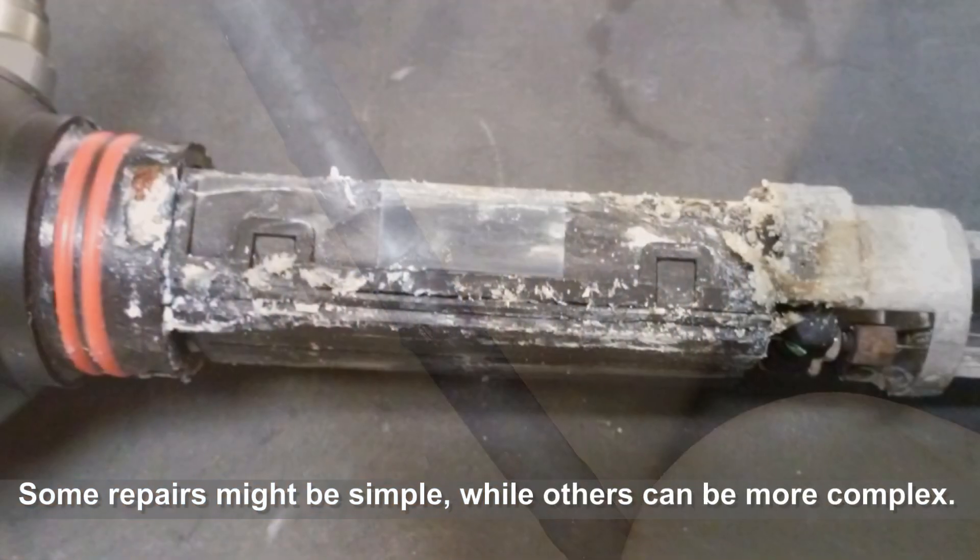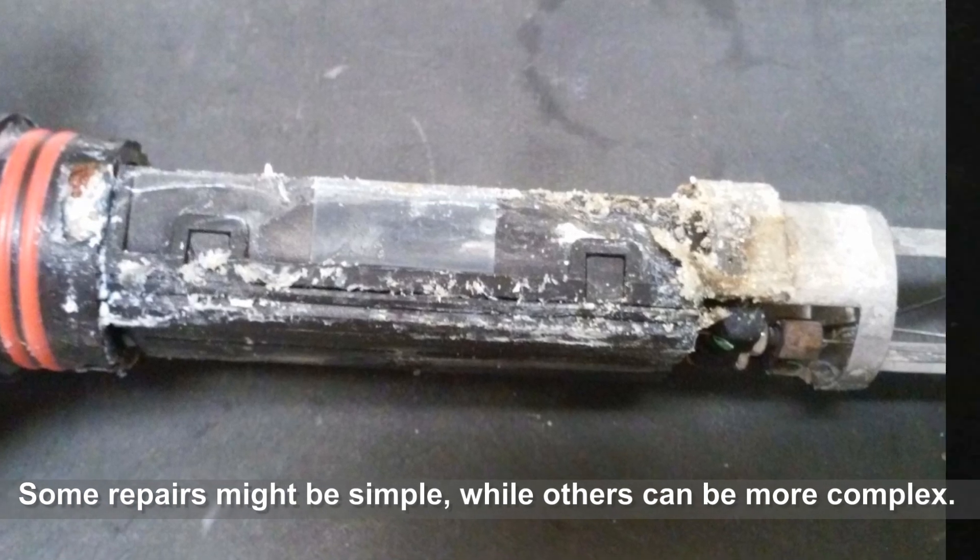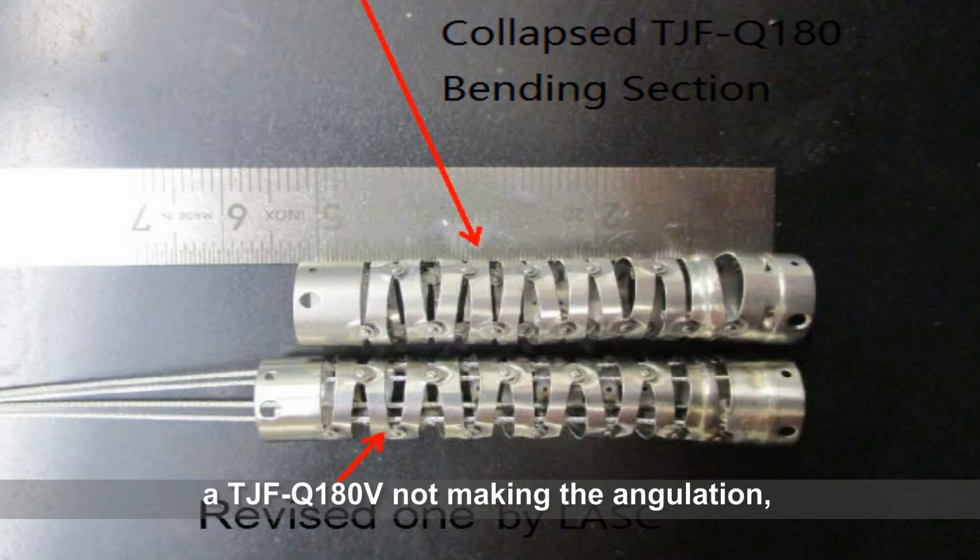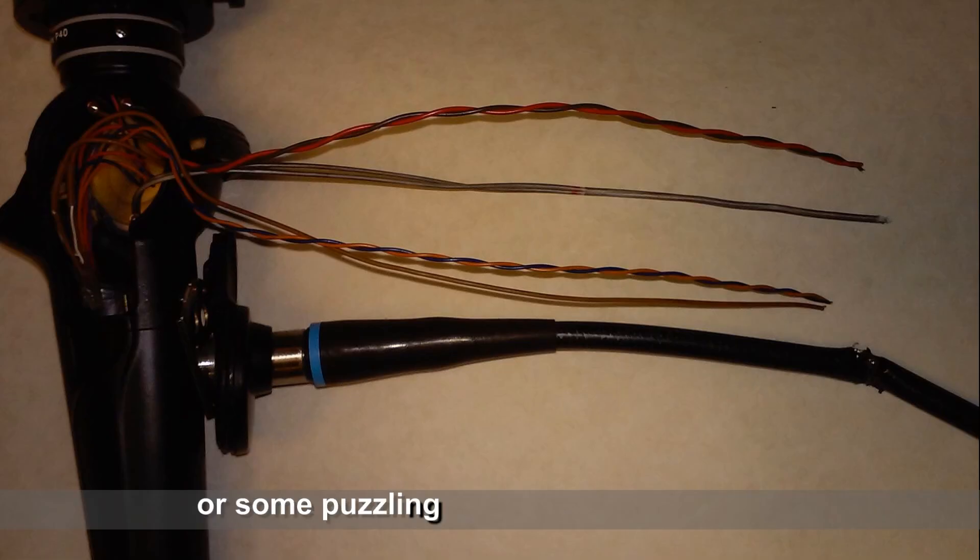Some repairs might be simple while others can be more complex. You might have a duodenoscope, TJF-Q180V not making the angulation, or some puzzling insertion tube problem like blistering, buckling, or discoloration.